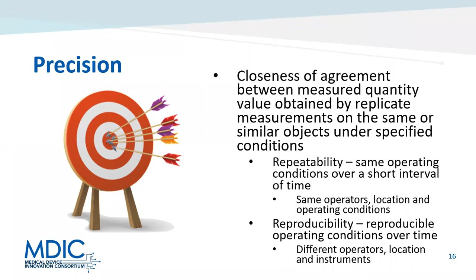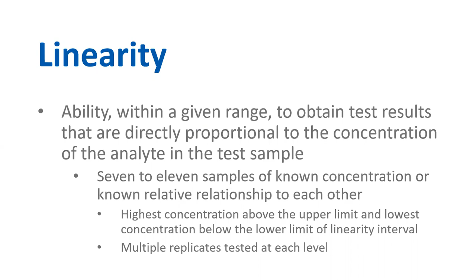For quantitative tests, it's necessary to determine or establish the concentrations at which the test is linear. This can be accomplished by using 7 to 11 samples of known concentrations or known dilutions. Testing of each sample is completed with multiple replicates, depending on the expected imprecision of the assay. The highest concentration tested should be above the upper limit, and the lowest concentration tested should be below the lower limit of the linearity interval. Next.